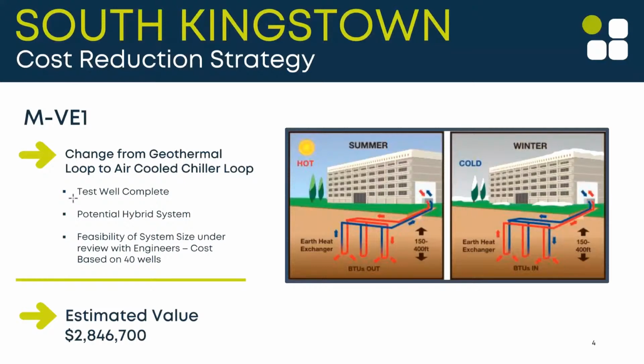The pilot study has been completed and was successful — they reached 800 feet and tested it for conductivity. I have that information in an email now, and the final report with a lot of scientific data is expected next week, requiring more study. What they've determined is that to handle 100% of the building's heating and cooling load, we'd need approximately 108 well holes, but we simply don't have that much real estate on this campus. The base estimate Gilbane used was 40 wells.